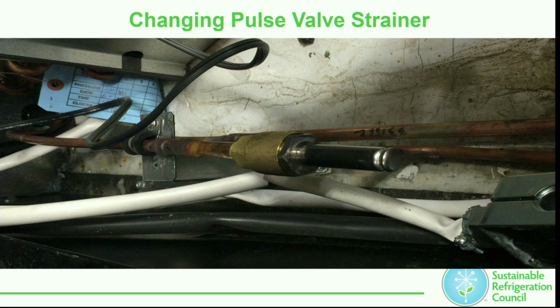When you're doing this, make sure that you're using 2 wrenches. If I ever see anyone working on any system, regardless if it's CO2 or chemical refrigerant, I don't care, use 2 valve wrenches when you're taking anything apart. Second recovery, because before we were dealing with a lower pressure, maybe 10 pounds of suction, 15 pounds of suction, now we have 200.